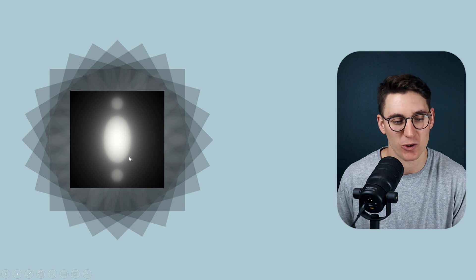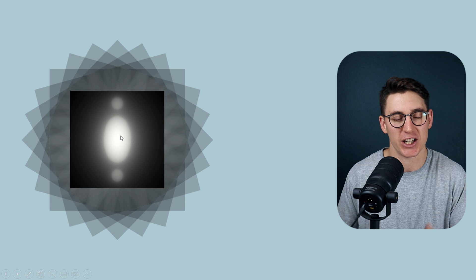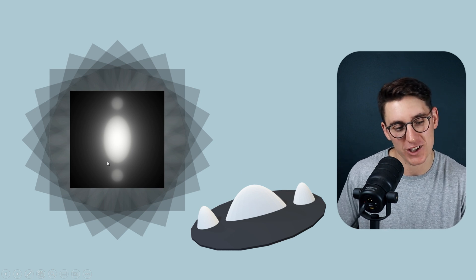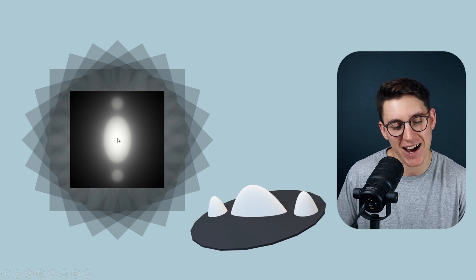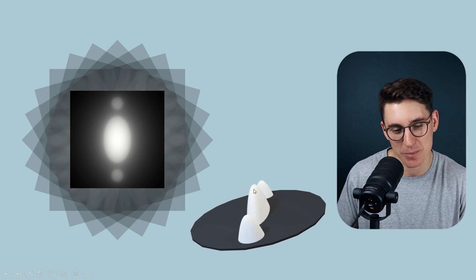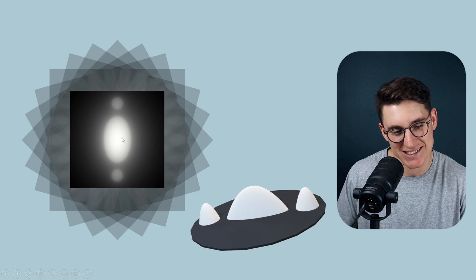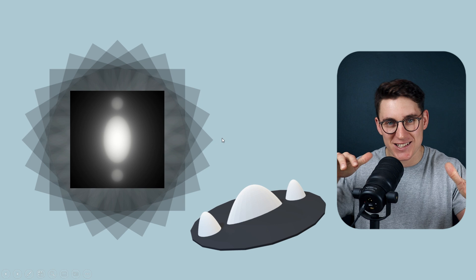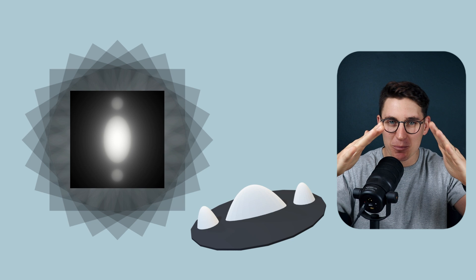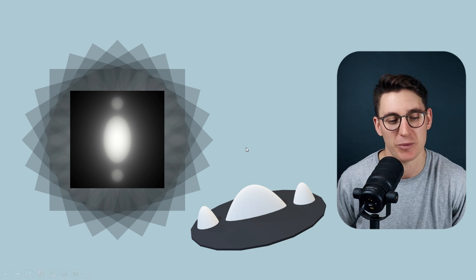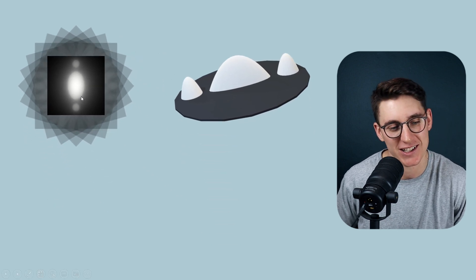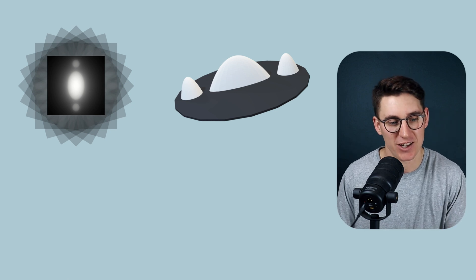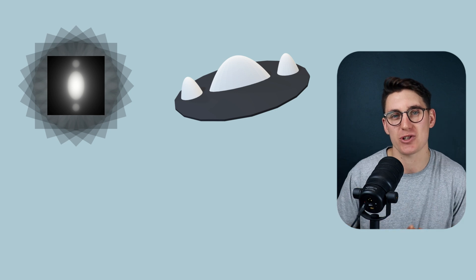Eventually we get an image that looks something like the one shown at the beginning of the talk — not perfect, with blurring on the outside, but we get a real appreciation for the underlying anatomy. We can also represent this data in a 2D plot: the more intense the signal, the higher the linear attenuation coefficient and the higher the peak. The signal tapers out towards the periphery of objects. What has happened through simple back projection is that smearing the data across the slice introduces blur into the image — we don't get crisp outlines. We need a process to take this blurred data and de-blur it. It turns out there is a mathematical description for how that blur was introduced: it's known as convolution.